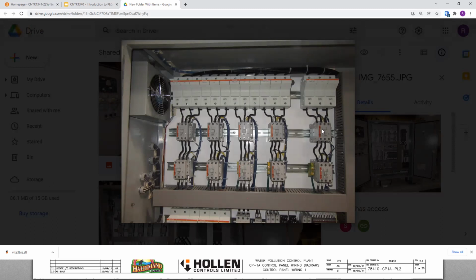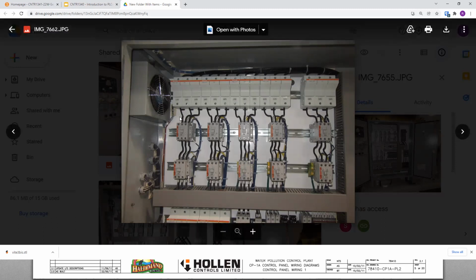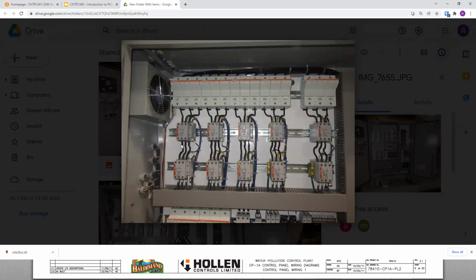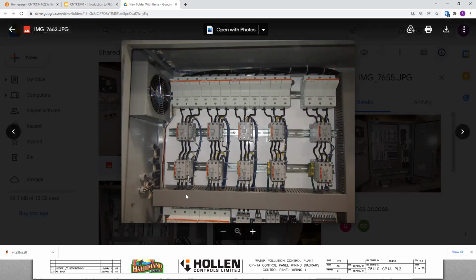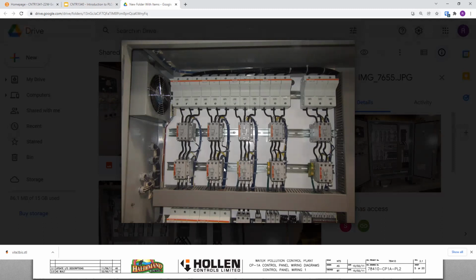When I started talking about SIL, the safety integrity stuff, this is an example of an industry where you could use safety equipment and wire up 2 sets of IO to a safety rated starter and all of that. But this is typically what you'll run into: companies will instead buy 2 starters at $80 to $100 a piece and a PLC and wire up twice as much IO and still make out $5,000 less than what it would cost to do the same thing with safety equipment. Lots of added expense.